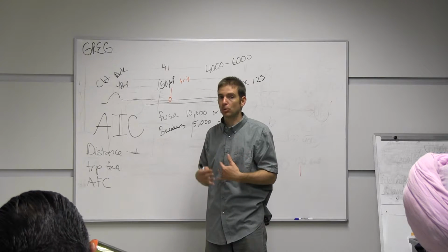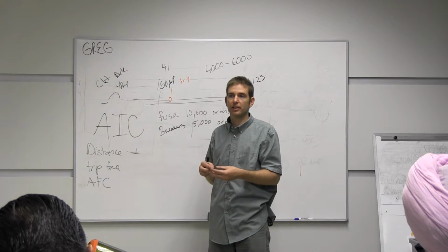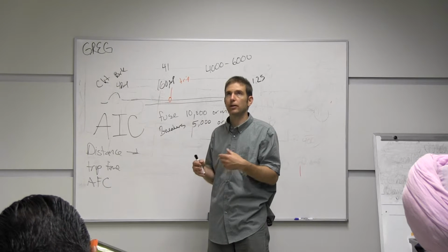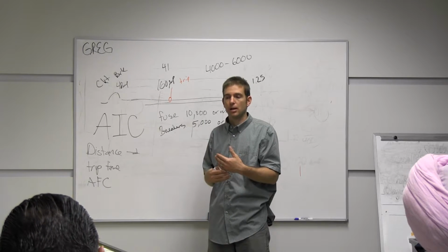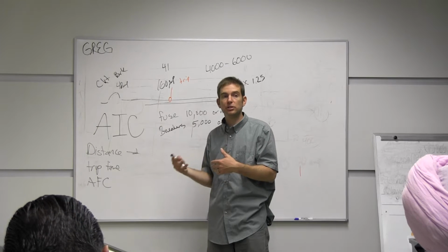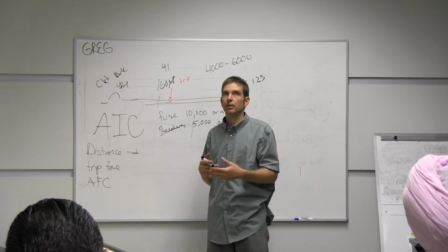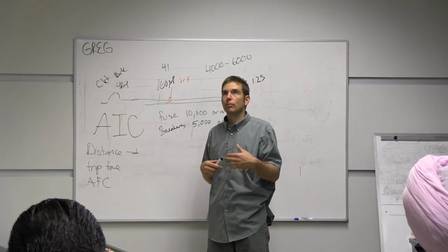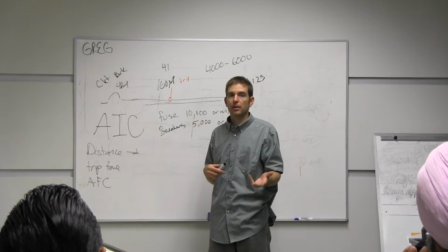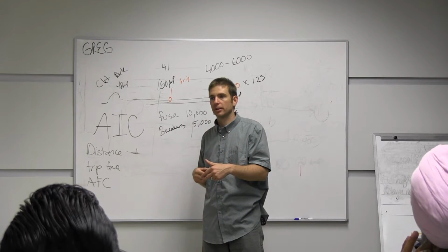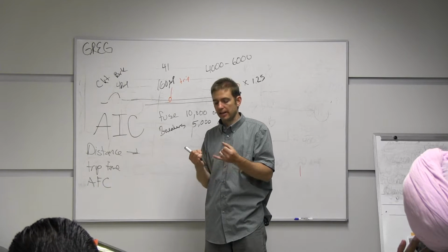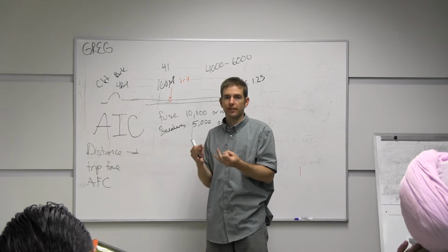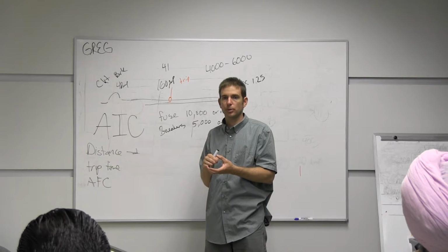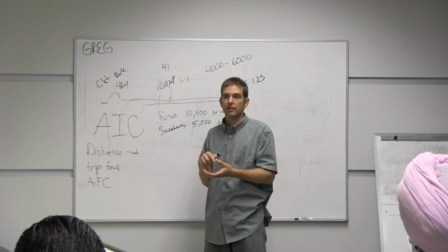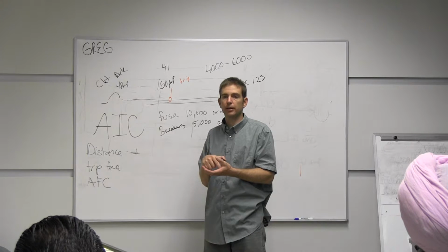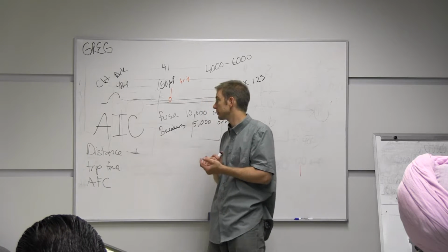Now maybe I used the wrong size wire, maybe I used bigger wire, so now I don't have as much fill, or I don't have as much room in the conduit, or maybe I'm using additional wires. So before I had 4 current carrying conductors in the raceway, but now I have 16 current carrying conductors in the raceway. When one conductor gets hot and another, they feed off of each other and they build the ambient temperature in the raceway until possibly the temperature erodes the value of the insulation and damages the insulation.